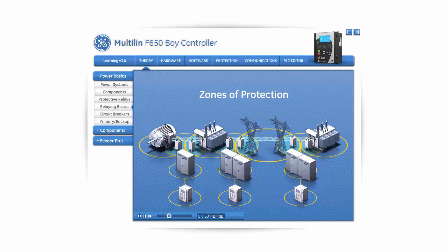A protective zone is an imaginary boundary around each major power system component. The boundary of a protective zone represents the region that a particular protective element covers. It is necessary for these zones to overlap to ensure proper protection. If two zones did not overlap and a fault occurred at the boundaries of these zones, it is possible that no relays would be tripped.